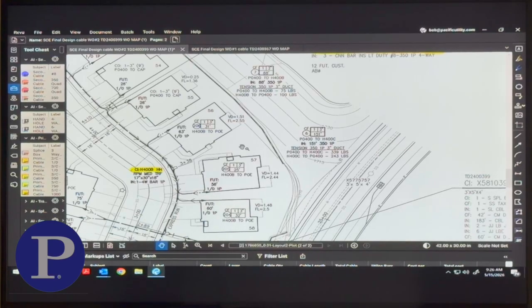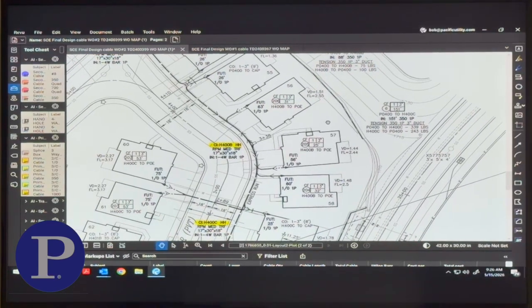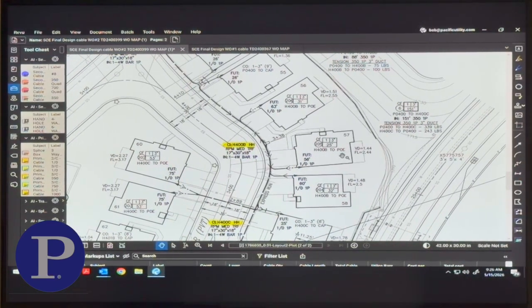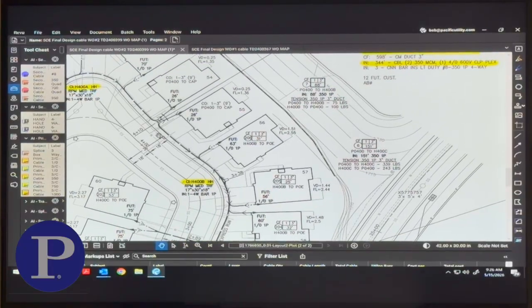In Southern California Edison systems, they are primarily pulling 350 secondary from the transformer to the handhole and handhole to handhole. They've gotten away from the 4-aught, 1-aught, anything like that. That being said, you should always check and verify. So when you look at this transformer, we know that we've got the 3 handholes.